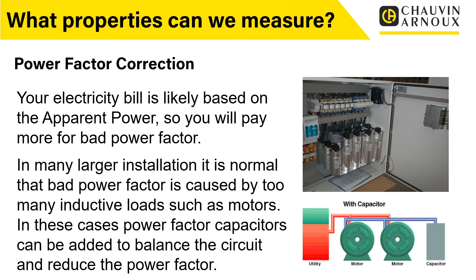Most installations aren't likely to have too many capacitive loads - it's usually inductive loads, motors, transformers, and so on, so normally you've got too much inductance. In these cases, power factor capacitors can be added to balance the circuit. If we've got too much inductance, we add capacitance, which brings it back into alignment - they cancel each other out, reducing the phase angle and increasing the power factor, trying to get it as close to 1 as possible. That gives us a more efficient electrical installation, with less waste, and it'll also reduce our electricity bills.